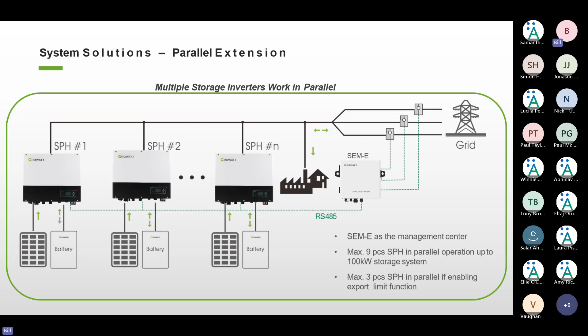And batteries, it depends. With the low voltage batteries, normally one system comes with like 40 kilowatt hours, so times 3 is 120. So yeah, that's quite big. But the difference is when you parallel this system, just remember you need not just a meter or CT meter, you need an SEM, we call it Smart Energy Management. This comes with the ShineMaster, a monitoring device built in. It can monitor multiple inverters, and the three-phase meter function is also on the right side in the SEM. So you don't really need an extra meter on this system. Just one SEM can monitor the system and also do the export limiting.